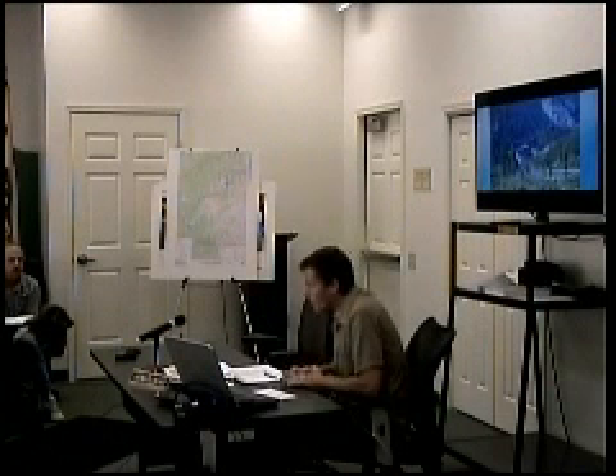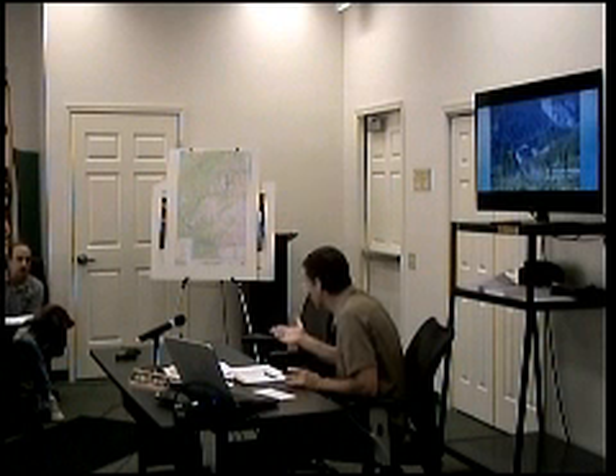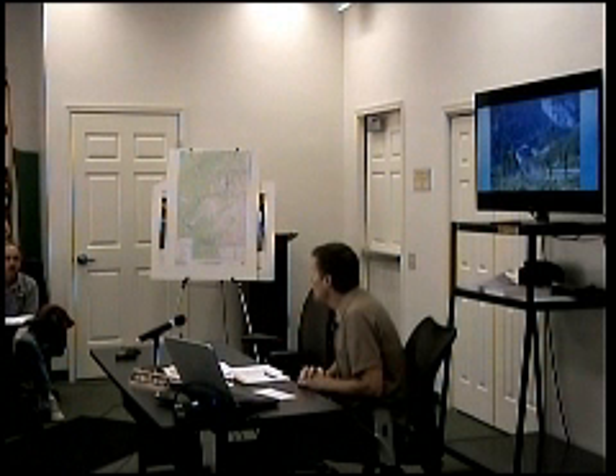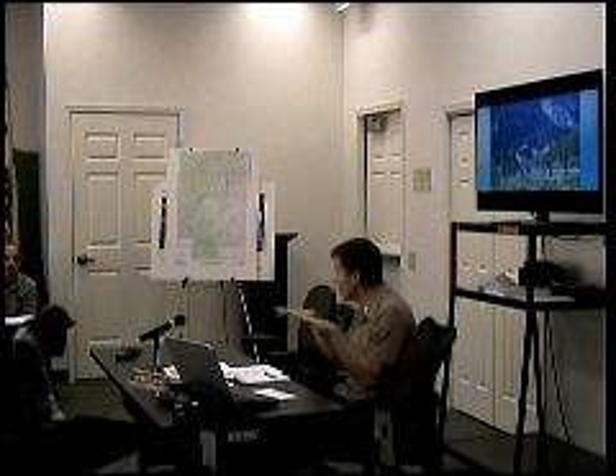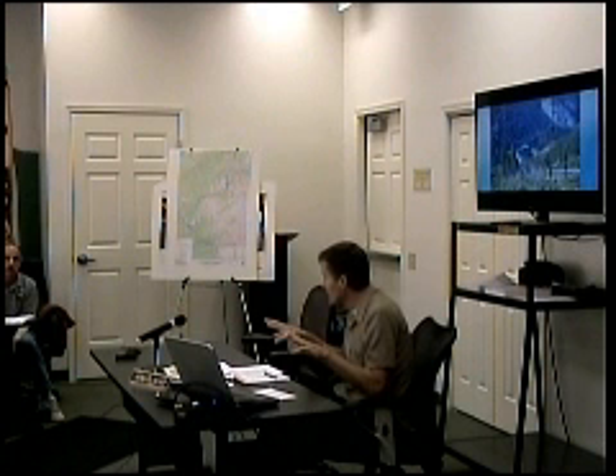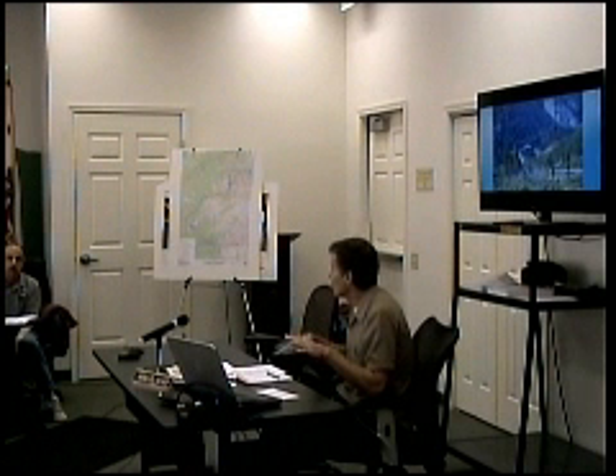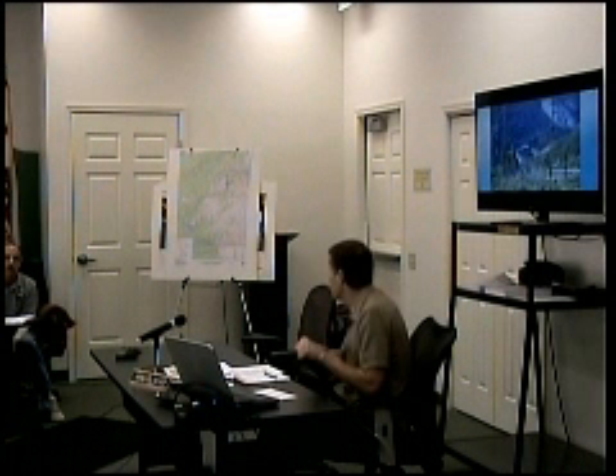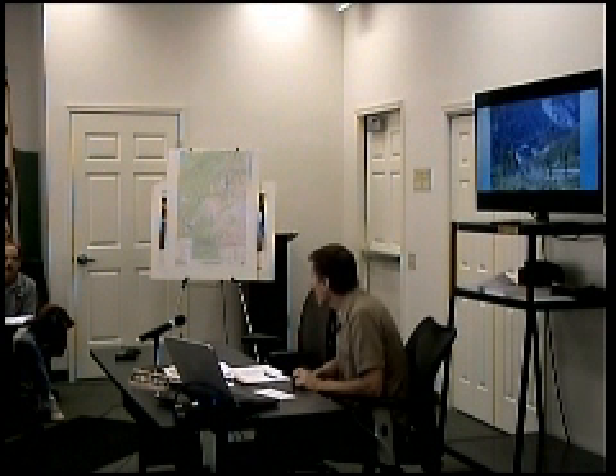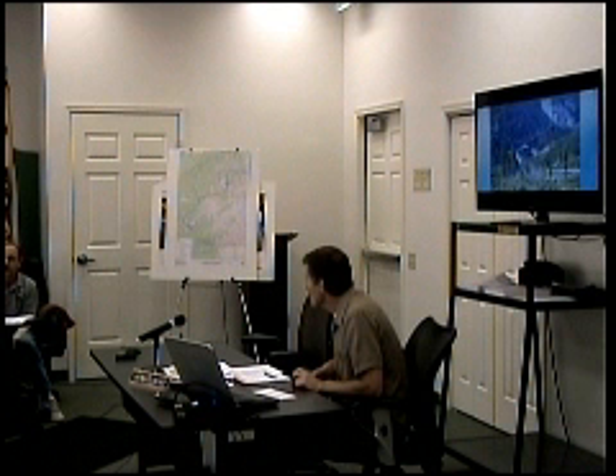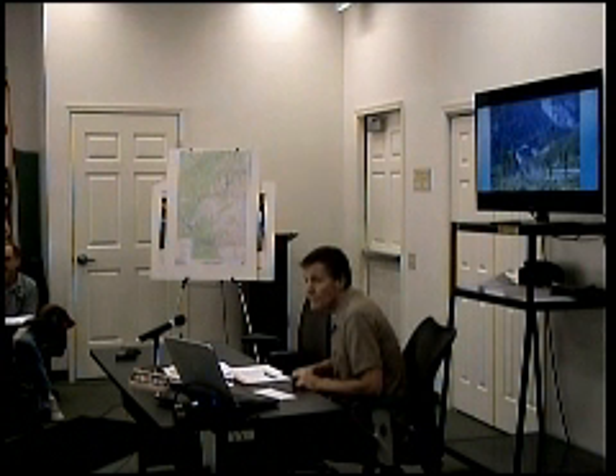It should be noted that if a tree did fall on it, and we did have a power outage, the first thing that would happen is our load-dependent start-stop system, which we actually turned off, would be turned back on, and the whole powerhouse would turn on at once. But it takes time for these generators to warm up. So yes, you're going to have a power outage, but as soon as those generators warm up, all 8 generators will be running, and then they'll start to drop off as it syncs with the amount of demand there is. Okay, and that transition time is on the order of how much? 5 minutes.